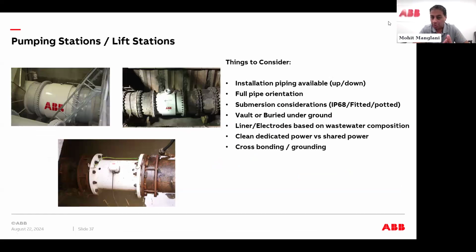So just to show you some pretty pictures, pumping stations and lift stations are one of the core applications out in the field that we come across. Things to consider, right? Make sure the installation piping is there, plenty available based on the mag meter that's being specified. Make sure you're putting it in an orientation such that the pipe is always full. If it's out in the field and it can get put underwater, you don't want to specify an IP67 rated meter. You want to make sure it's IP68 rated for the amount of water that's going to be on top of it. Validate if you want to put it inside of a vault, which is good practice, or whether it's buried underground under rock and dirt.